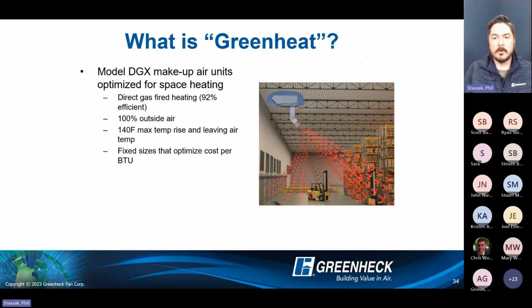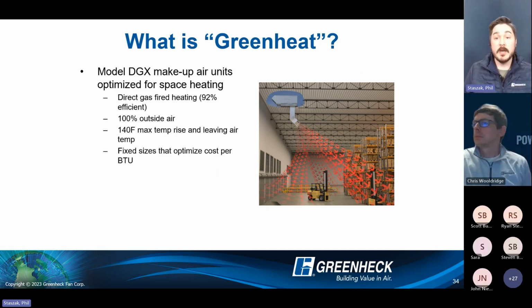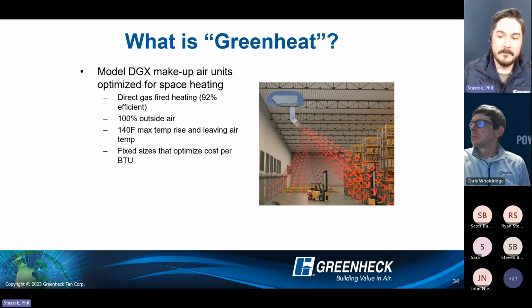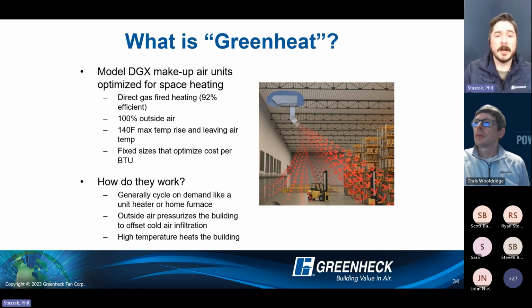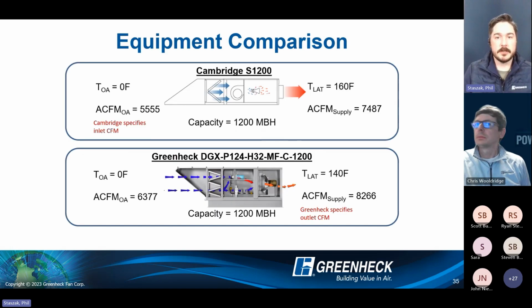Again, it does populate though. For an Amazon distribution facility, for example, a 1,000,000 square foot facility, you can get away with as few as 8 units to effectively heat and ventilate that very large space. So it's a very effective way to approach both ventilation and heating for these very large spaces. And they'll cycle on demand for whatever the space condition is, very similar to your home furnace. And at the elevated discharge air temperature, you get more usable BTUs per CFM.